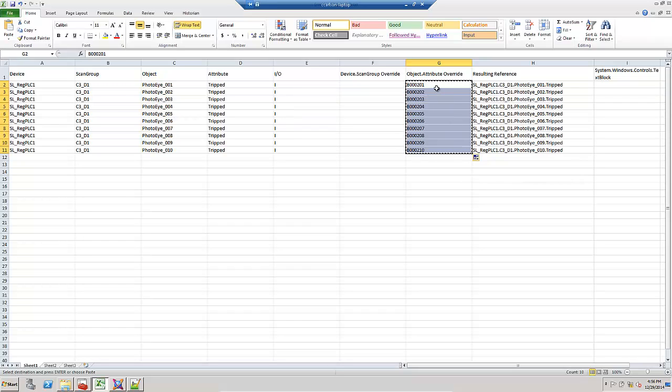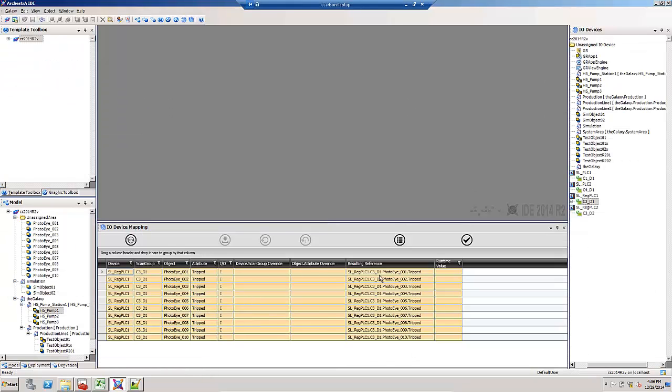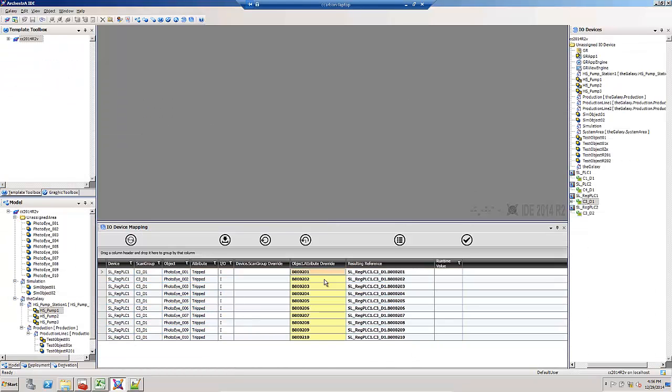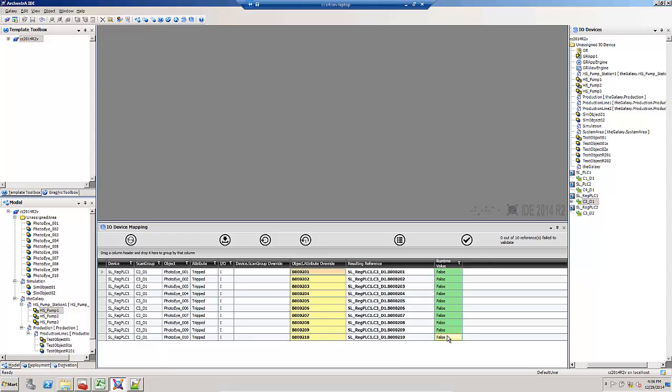Then I'm going to copy just that column back into the IDE. Validate them to make sure I typed them in correctly. The PLC values are false but they're green, which means they validated correctly. Then I can accept and apply those overrides. That's a convenient way to make bulk changes.